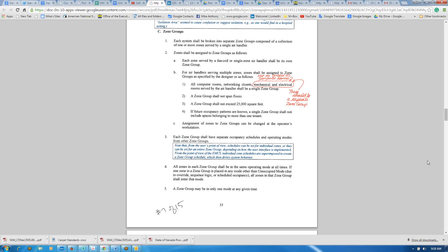I think ASHRAE has got to divide it up by the county, if I'm not mistaken. We'll move on to page 33. Page 33, paragraph C.2.B.1, where it lists the zone groups. It puts computer rooms, network closets, mechanical and electrical rooms all in the same zone. And my thought is that the temperature for computer room and networking closet is more sensitive than it would be in most mechanical and electrical rooms. Maybe those two spaces should be put into their own separate zone group. I know for mechanical equipment, mechanical rooms don't even get cooling because of the heat. You can definitely have different set points for those areas as well.